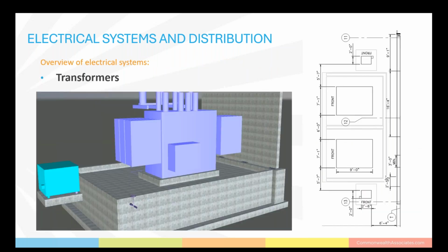Let's take a brief look at transformers. Here's an example of a 3D model of a transformer, and on the right is a plan view of 2 auxiliary transformers. Transformers will typically sit outside as they're physically very large and oil-filled. Generally, they require blast wall if located near other equipment, and they will typically require oil containment even if environmentally friendly oil is used.